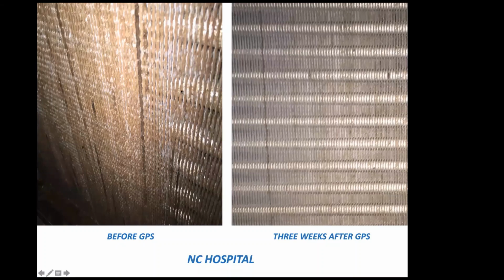But 3 weeks later, when we came back to just discuss how the systems were operating, this is what the same coil looked like with no mechanical cleaning between day one and the 3 weeks out. It's killed the mold that was growing, and when the coil is condensing, it just washes that mold away right down the drain. So no mechanical cleaning between the before and after. So you can imagine how much heat transfer that mold was impacting on the coil versus now.